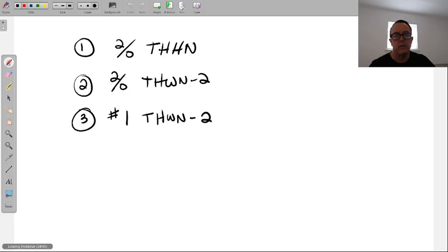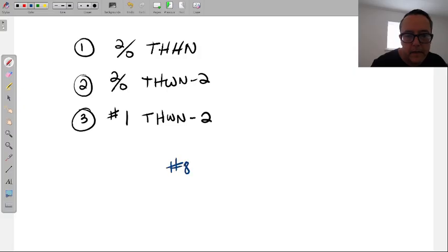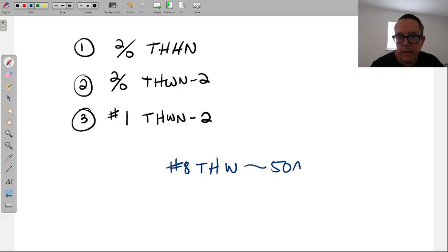All right, so I'll head over here to where we were, and we'll do a little bit of math. The first thing we have to do is find the ampacity of a number 8 THW wherever it lives, and it happens to live in the 75-degree column, this one. 50? Yeah, 50 times 0.7. It's 35 amps. Nine conductors is not a huge number, but it's already a lot.